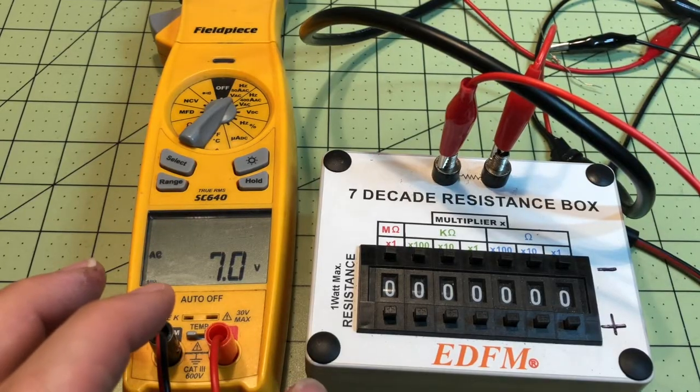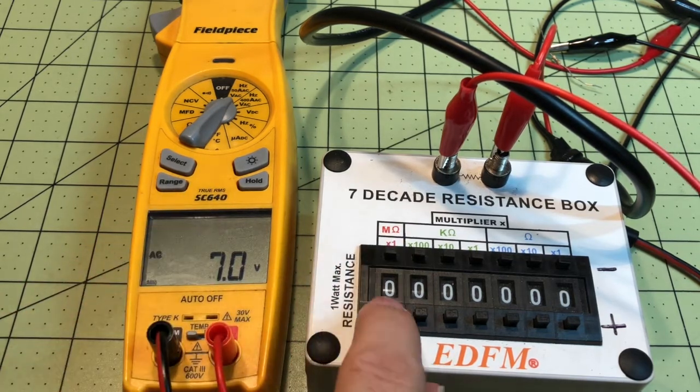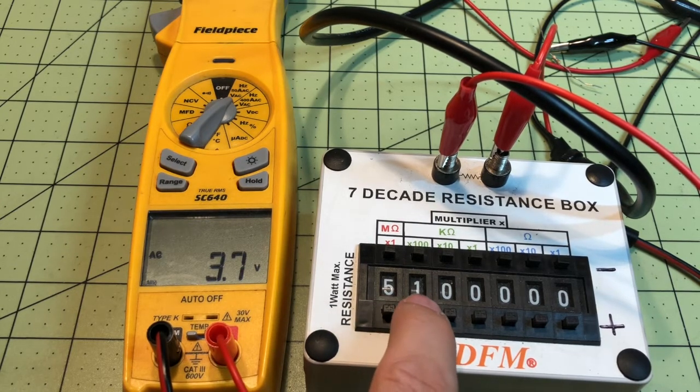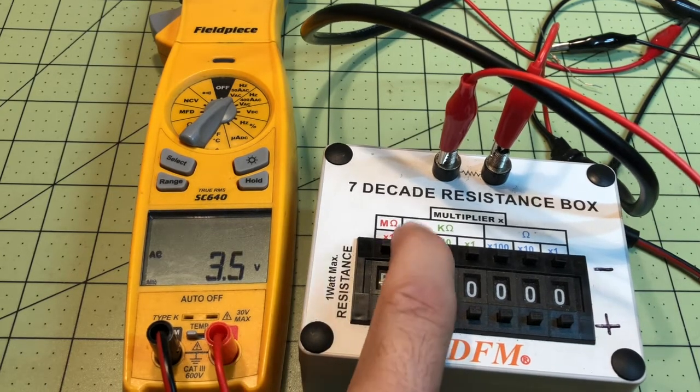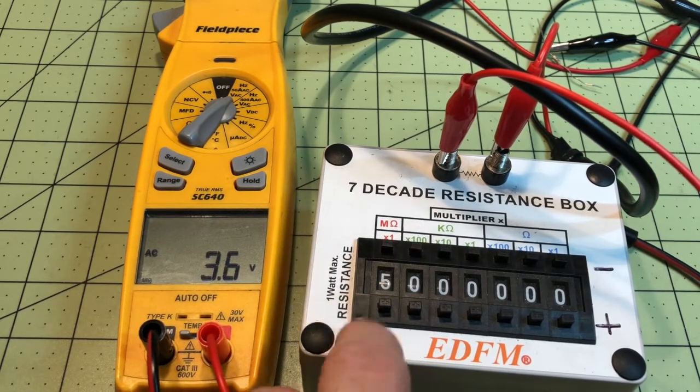This is the Fieldpiece SC640 multimeter. Going to 1 megaohm — that's not going to get us there. Stepping up: 2, 3, 4 megaohms... 5 is close. Settling on 5.1 to 5.3 megaohms — we'll call it 5 megaohms input impedance for the Fieldpiece.